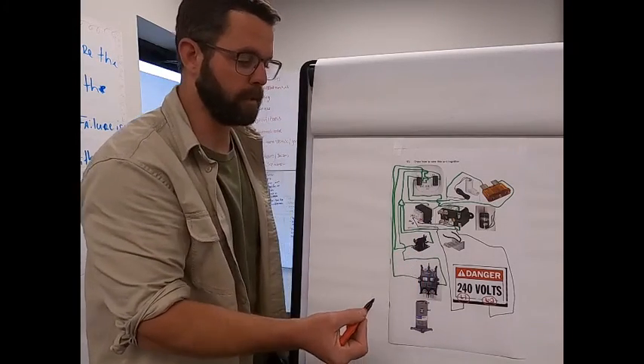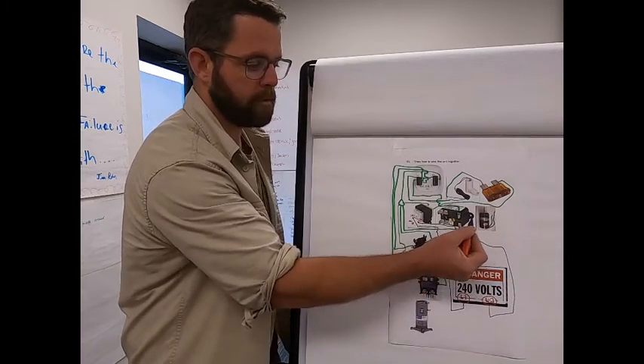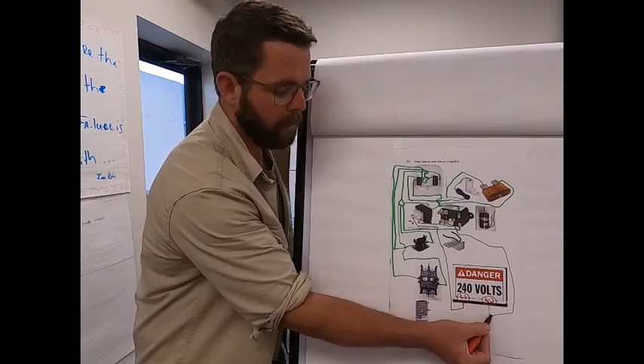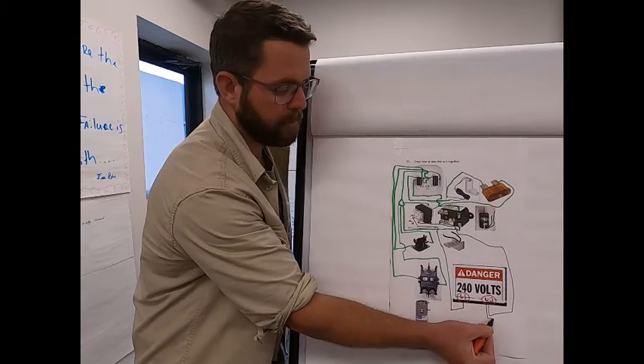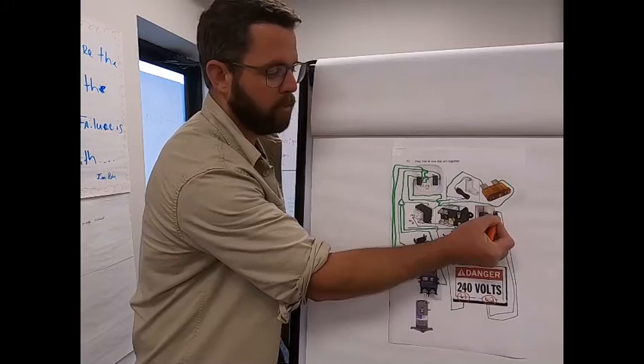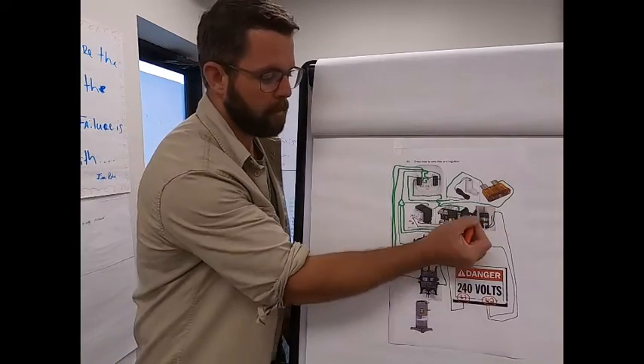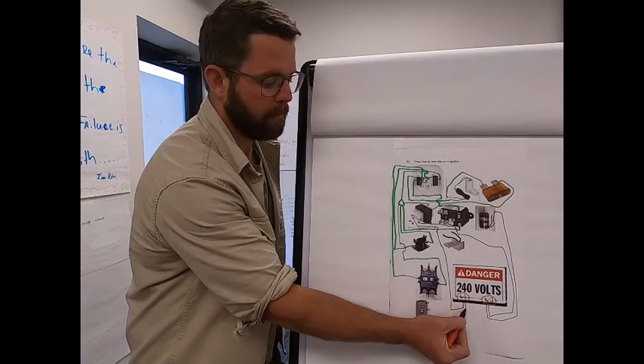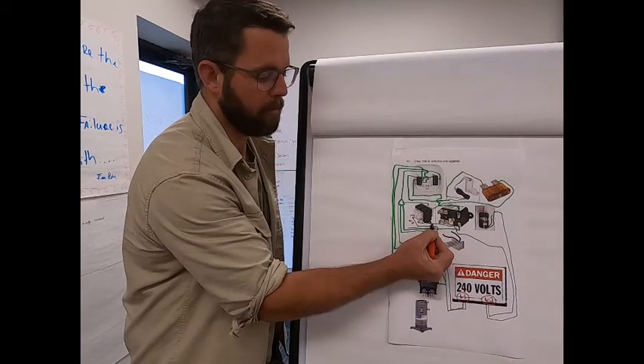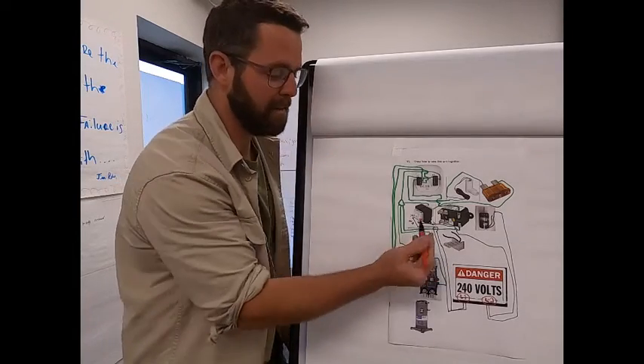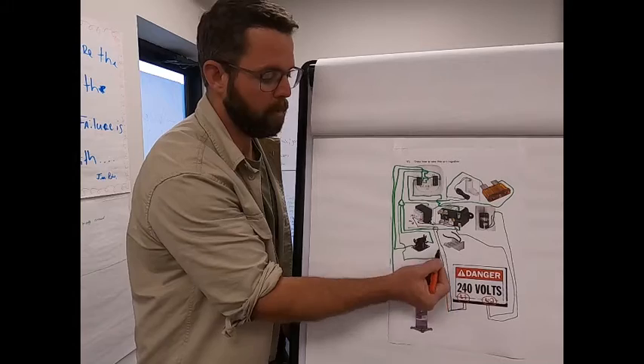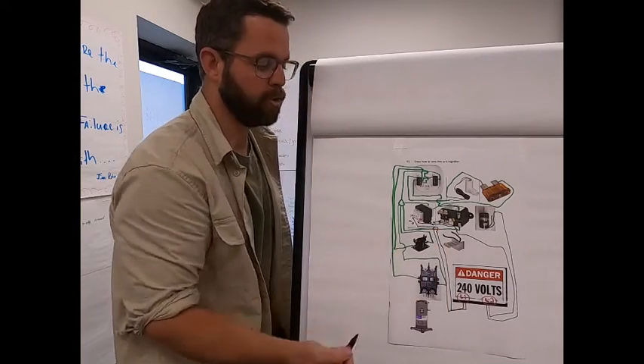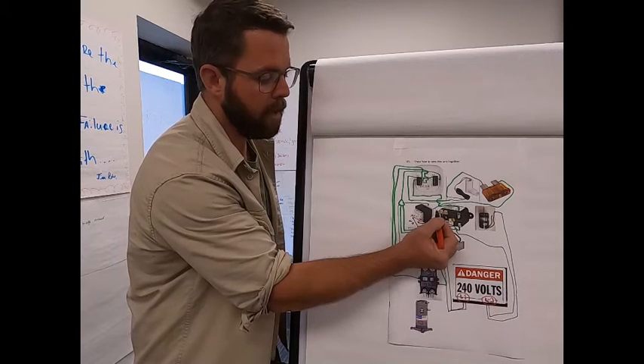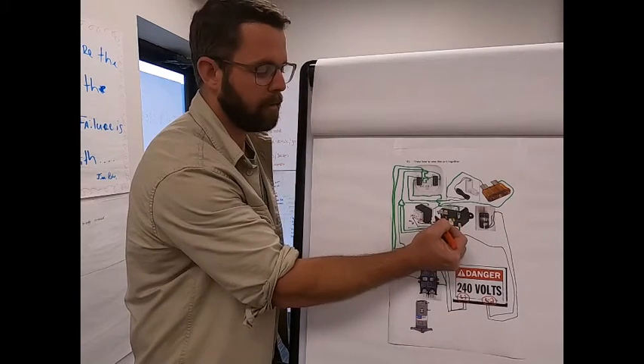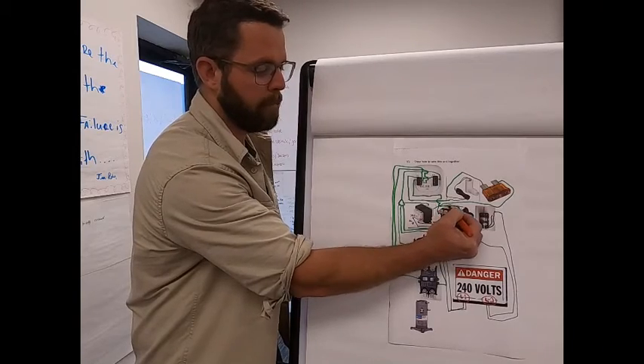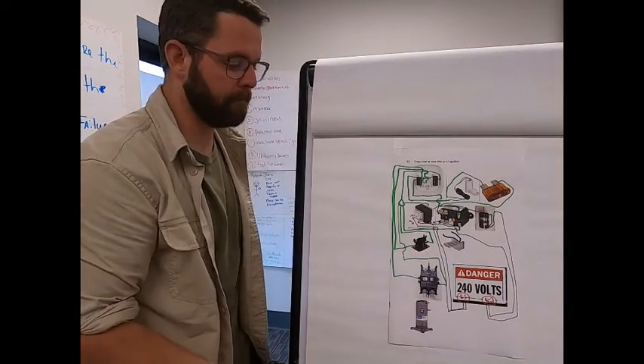Now the rest of our major components need to be powered. For our blower motor, which is depicted here, our blower motor will get one side of direct voltage. L2 will go directly to one wire on the blower motor. The other wire will be powered by L1, but first it has to run through the breaker. I'm sorry, not the breaker, it has to be broken by the relay. So it will come from L1 into this pin in the relay, which is normally open. Then the other run on this relay, which is the normally open circuit, will come and attach to the other leg of the fan motor.